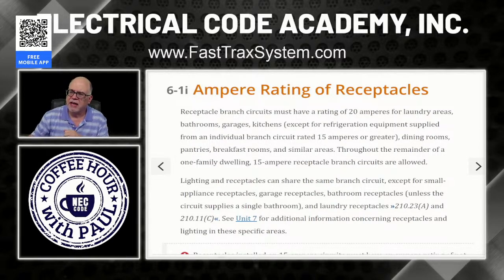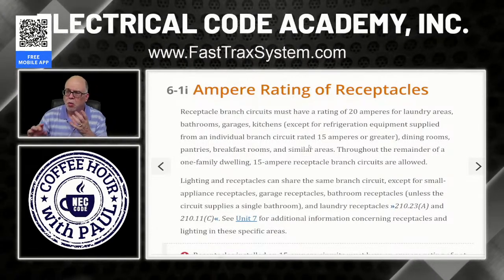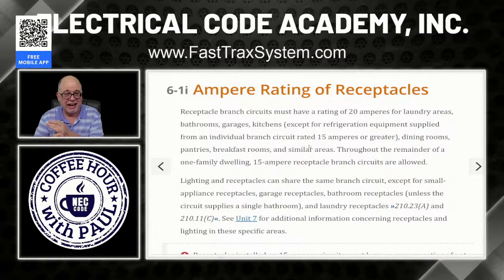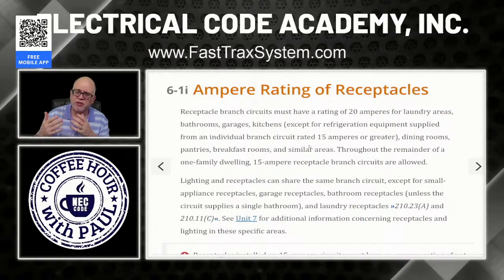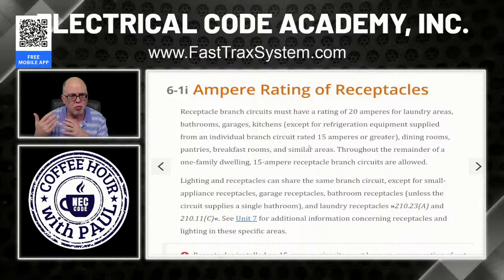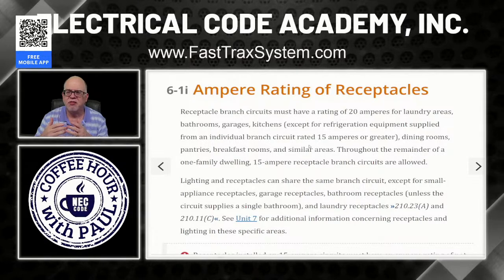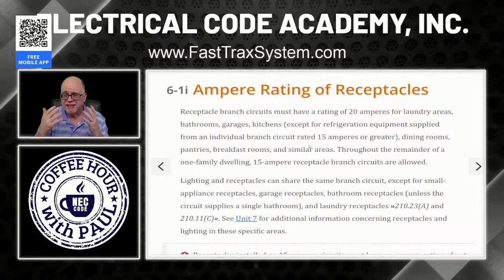Okay, all right, so let's look at it here. And of course, as always, we're going to do a little bit of a lesson up front and talk about what branch circuits in a house have to be 20 amp, and then which other ones can be 15 amps. Understanding that you could do the whole house in 20 amps if you wanted, obviously not the larger loads like ranges and whatnot. They'll have their own calculations, their own receptacles, their own ratings. But we're talking about general purpose and things like that. If you want to do everything in 20, you could. But we're going to talk about what's required to be in 20, and then everything else could be 15 amp when we're talking about general receptacle applications.